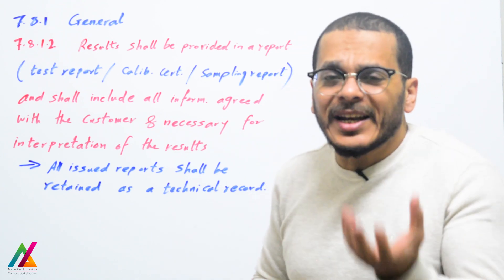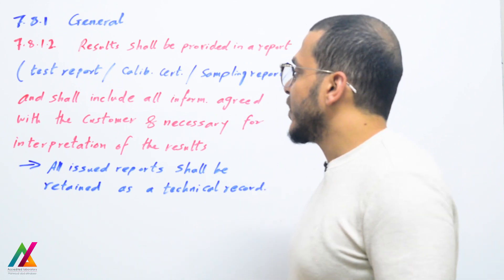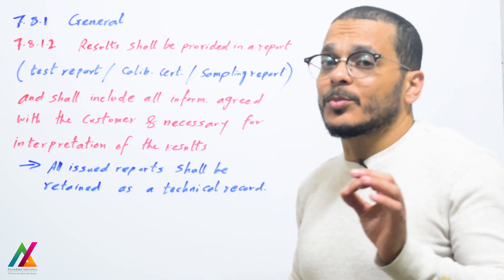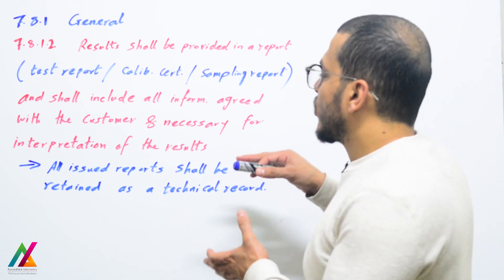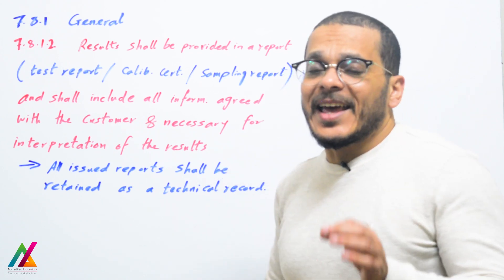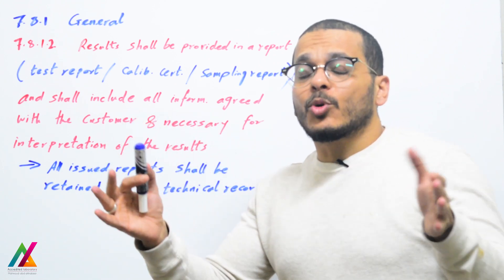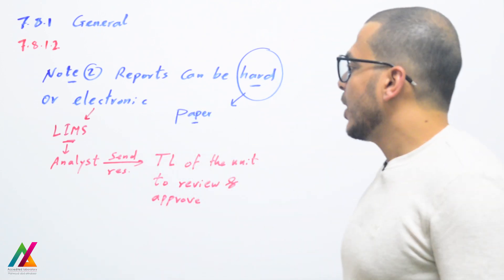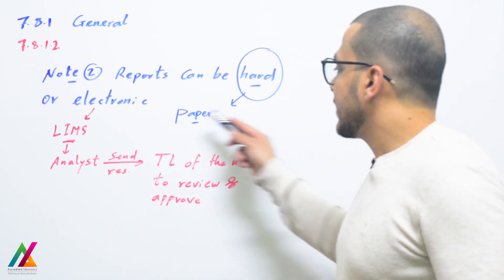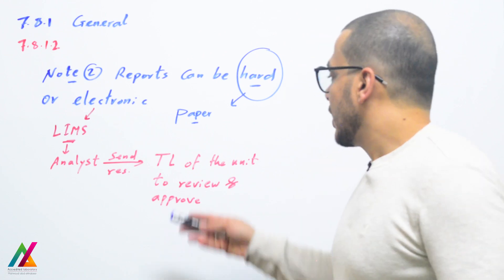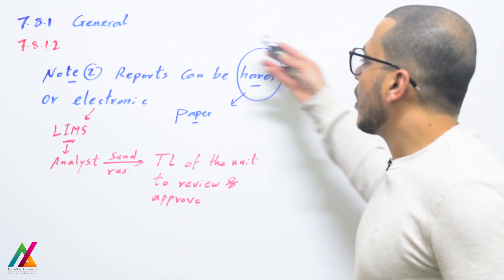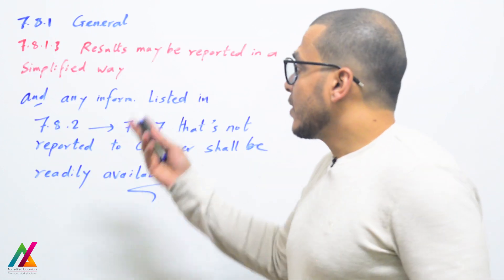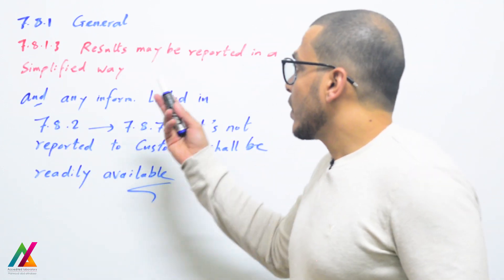The report shall be simple and clear for the customer to facilitate easy interpretation of results, and shall include all information agreed with the customer and necessary for interpretation. All issued reports shall be retained as technical records, so the final report is a technical record. Reports can be hard copy or electronic — if you have a LIMS inside the lab, the analyst will send the result to the technical lead through the LIMS for review and approval. Paper documents are still recognized in this edition.